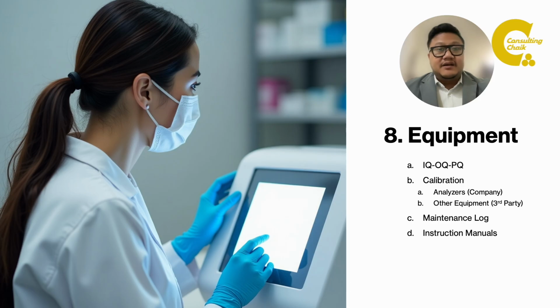So you just need to ask the analyzer company to give you the IQ, OQ, PQ document with the raw data. Okay, for calibration, what you need to understand is for the analyzers, you just need to take it from the company directly. So, for example, if you have a clinical chemistry analyzer, your electrolyte analyzer, immunoassay, or cell counter, ELISA, you just need to ask the company to give you the calibration every year. And for other equipments like your micropipette, centrifuge, thermometer, you have to get an NABL accredited certificate. So in the certificate, the calibration agency must have the NABL logo saying that their lab is NABL empaneled, and those equipments are under their scope of calibration.